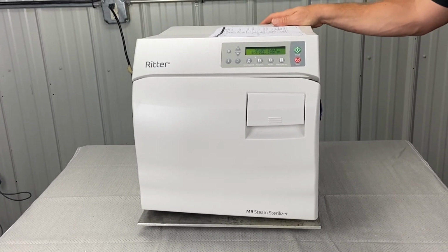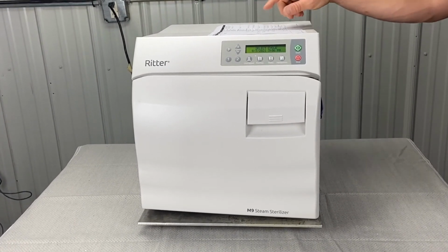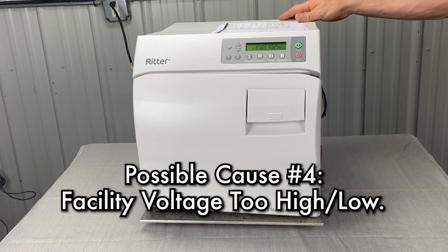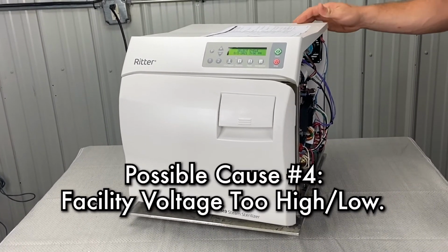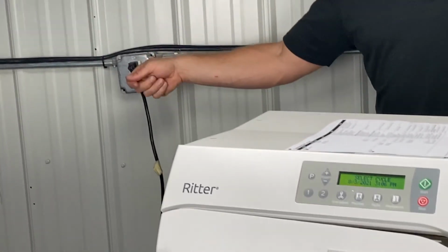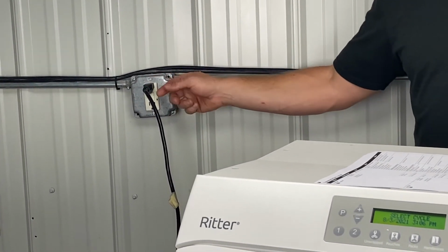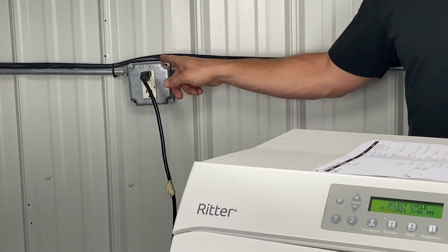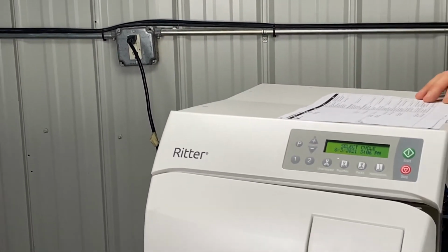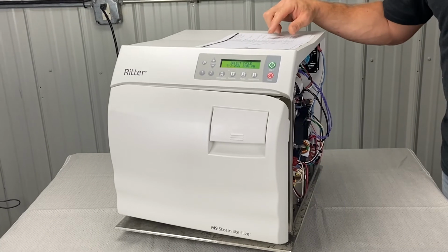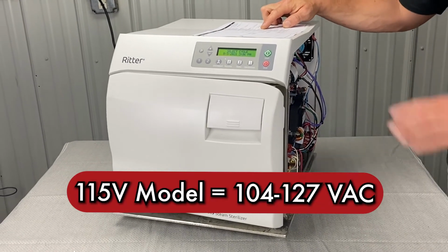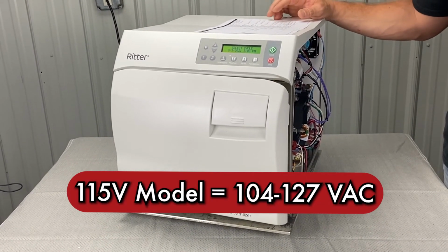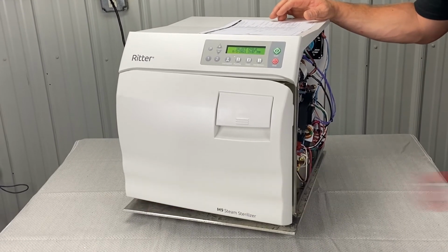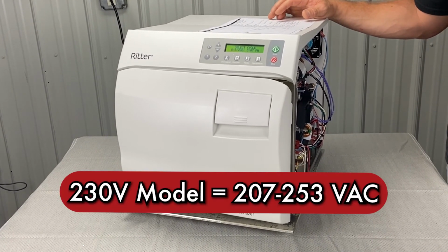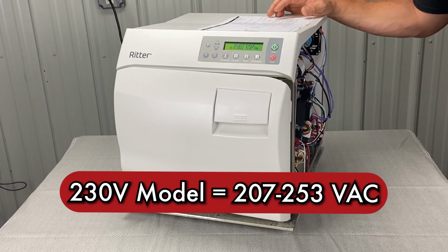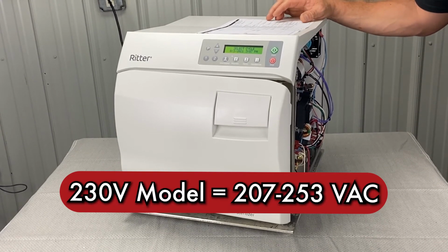And then we can do a facility voltage test. You would need a multimeter for that one as well. Basically, you would unplug the unit from the wall, plug your multimeter red and black leads in there, and you should read voltage for a 115 model, which is this model. The voltage needs to be 104 to 127 volts AC. And then for a 230 model, it needs to be 207 to 253 volts AC.